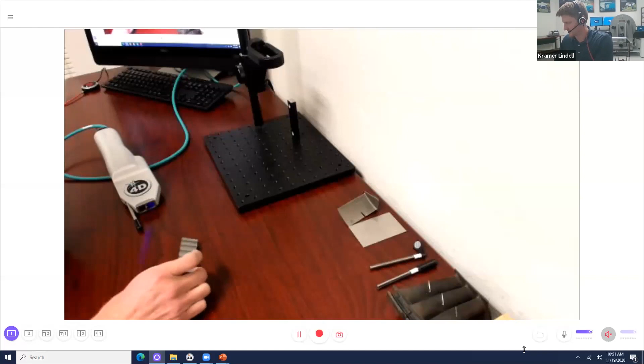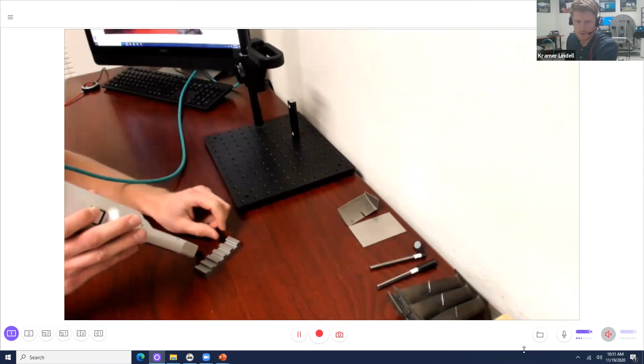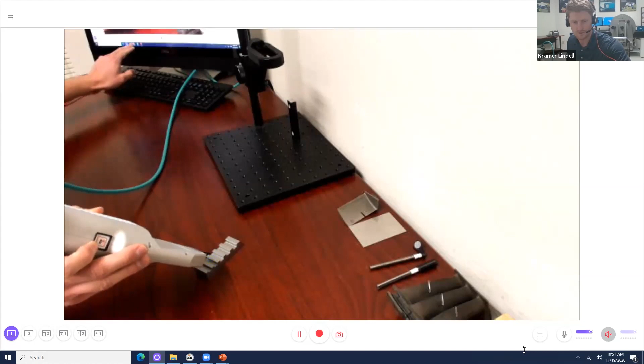We've done a significant amount of testing, as Eric alluded to. So I can go ahead and take some measurements on this standard here, just by putting the inspect up to the part itself. I'm going to put the inspect down, have that blue light reflect off of that surface. And when I'm in focus, I'll click this button and take a measurement. So I'll switch over to my live video here. That left screen is my live video. I'll get this in focus. When my surface is green, that means I am good to go. I'm in focus. When that happens, I can click that button and I'll get a 3D surface map of that area.